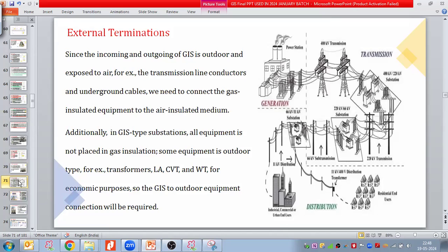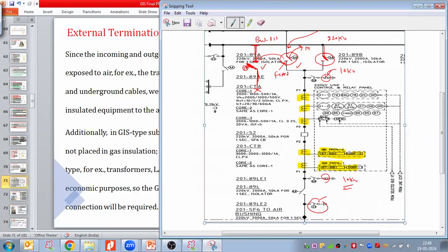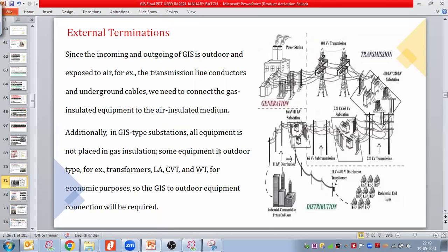So now coming to the termination of the GIS. All the equipment that we take: the bus bar, disconnectors, then switch, CT, breaker, CT, disconnectors, and then the high-speed earthing switch. All these switchgear equipment come under the GIS. We have taken these equipment models one by one. Now let us discuss the connection between GIS and AIS, the external termination of the GIS.